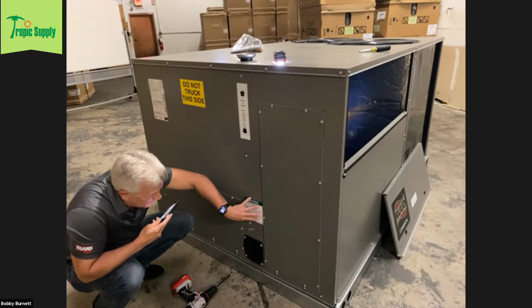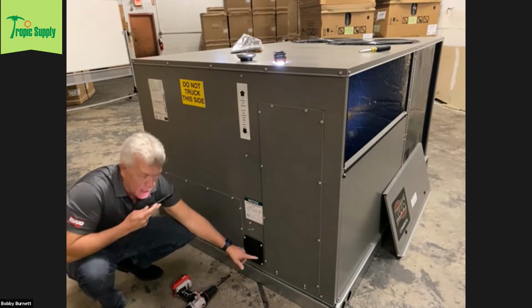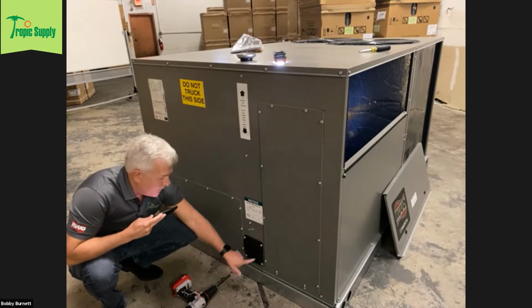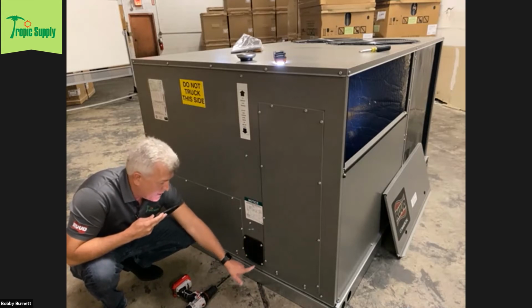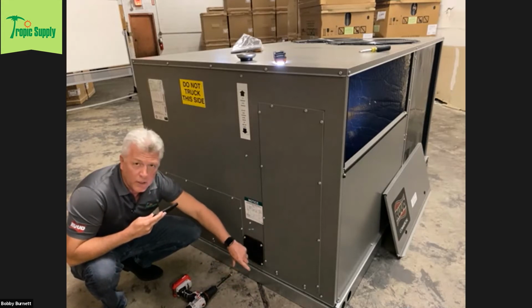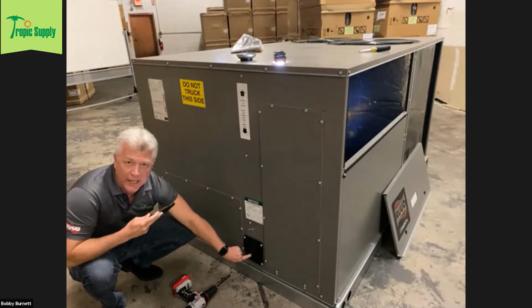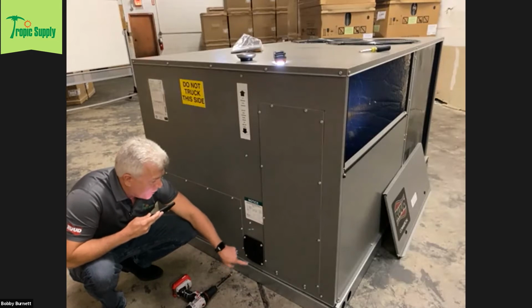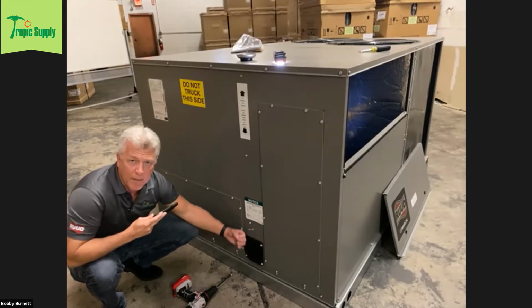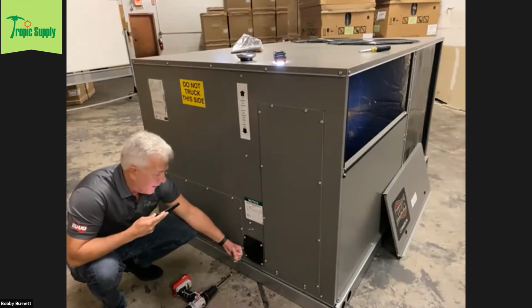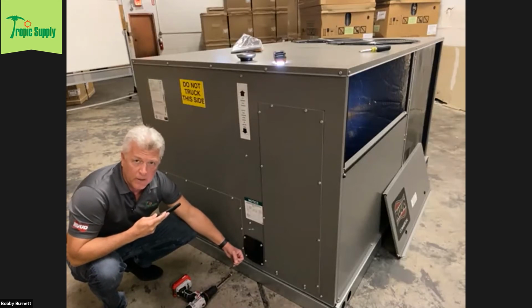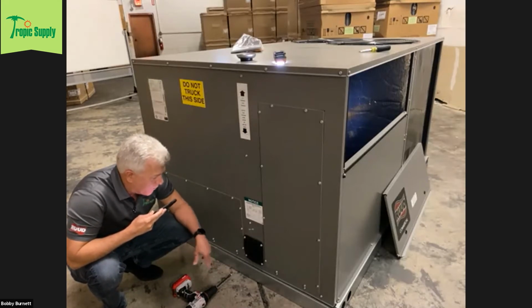Now, what this also allows you to do is, instead of having a side drain, you can bring a PVC pipe out here and put a street elbow into a regular PVC elbow, go back into this fitting here, and now you've just looped that drain back into here, and you can come out the bottom of the unit with a bottom drain out of the unit. Okay, and I'll show you a little bit better how that works.